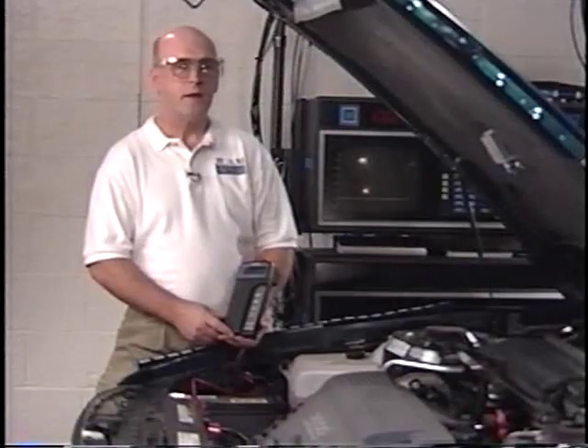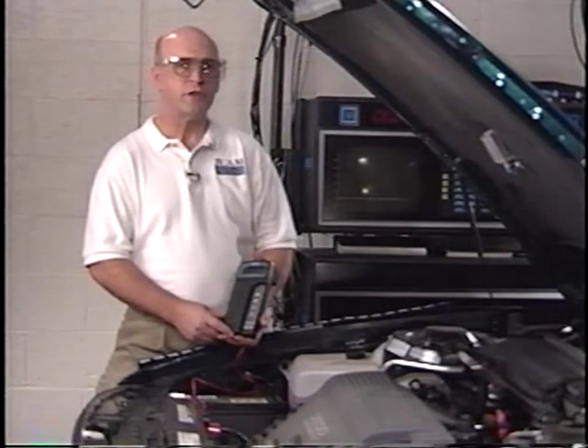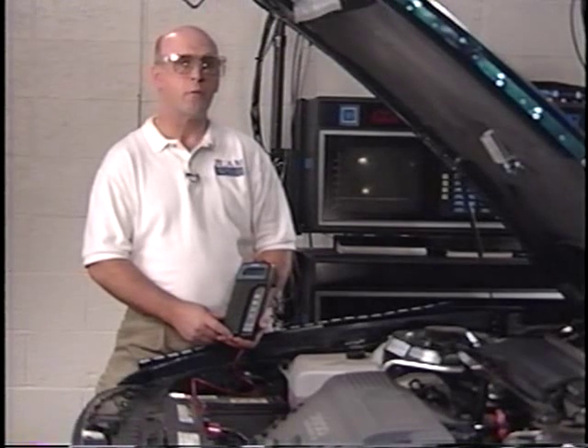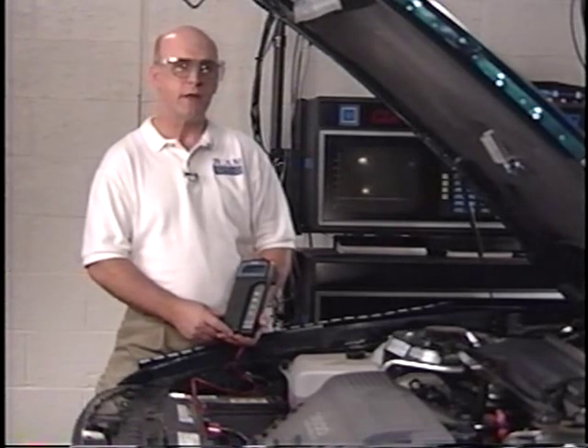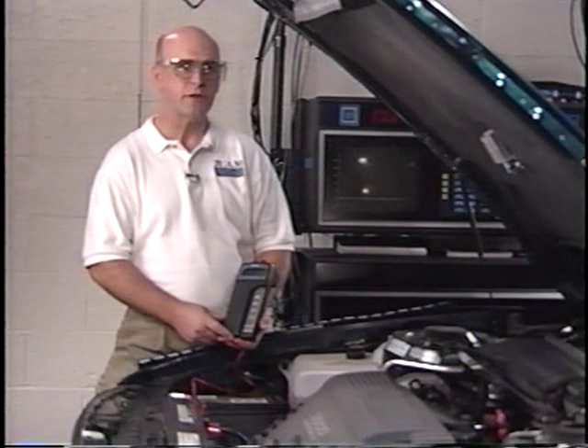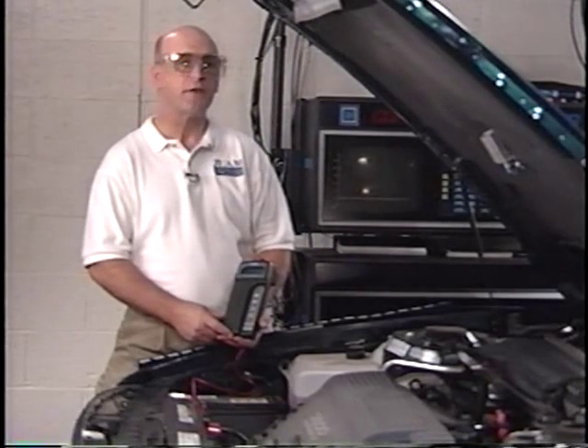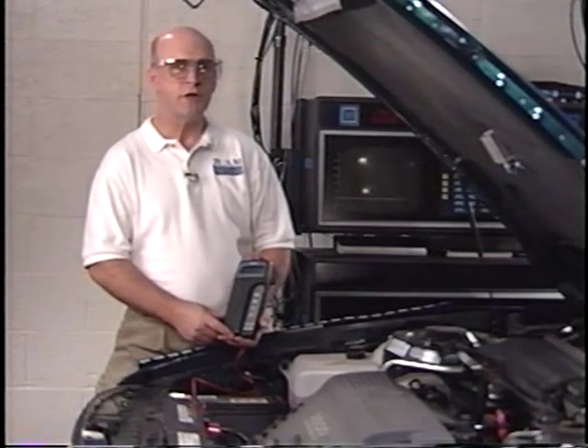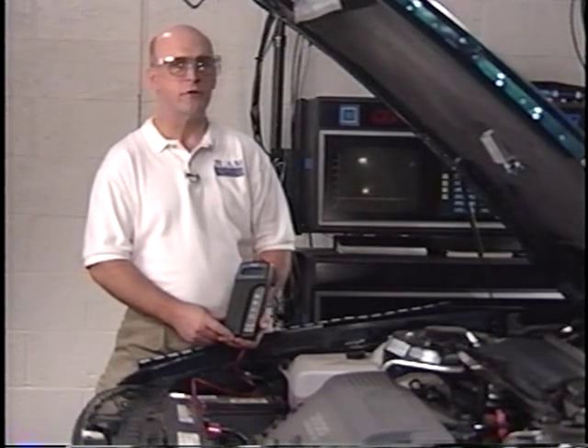your customer. If the message in the window is charge and retest, that means the battery falls into a category where it can't make a sound decision. It needs to be energized or fully charged to identify whether or not it's healthy enough and serviceable. Fully charge the battery on a current limited charger before attempting to retest.